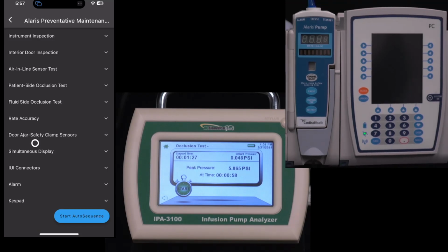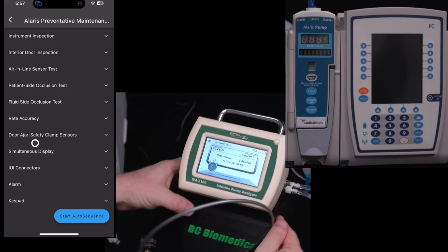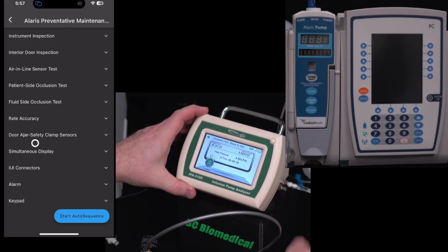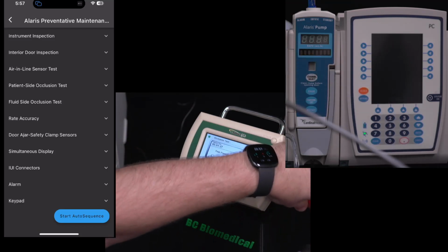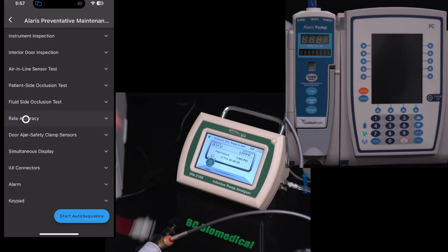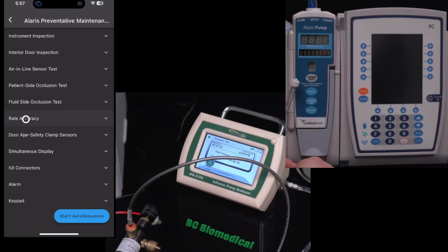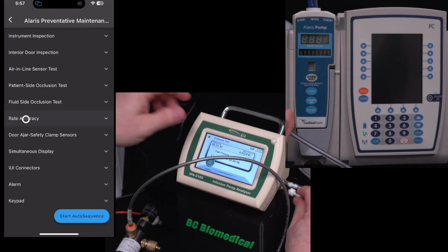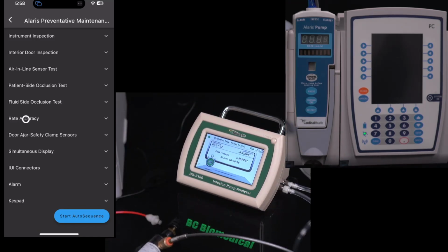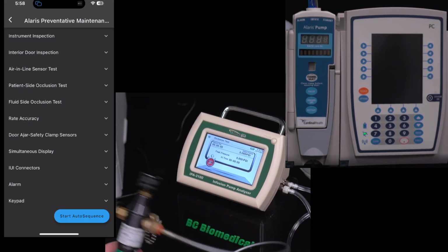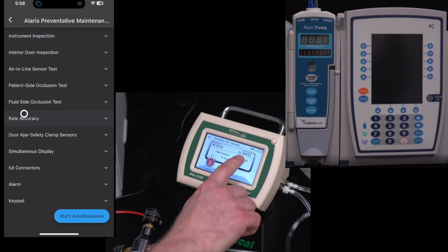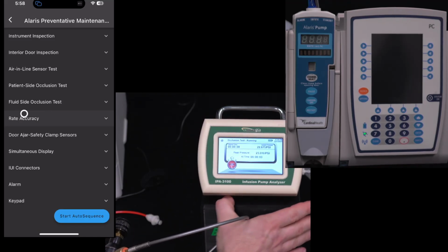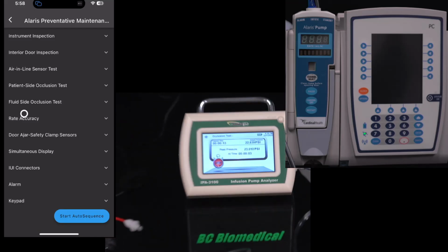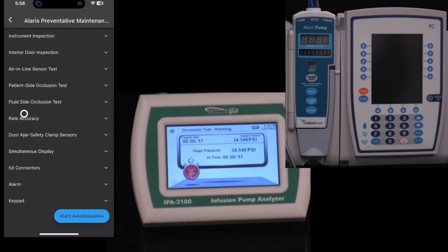So let me zoom out a little bit too, probably this one here. All I have to do is disconnect the inlet tubing here, and I've got my handy dandy hand pump here, so I can plug this in with the correct fitting. It's always a matter of having the wrong fitting, right? So plug that in there, plug this into my hand pump, and then as I apply pressure, I'll hit start. As I apply pressure, now I've got a manometer, and I've got the instantaneous pressure. Let's see if I can show that. Ooh, bad reflection there. Show that right there on the screen. Now you've got a manometer that you can use for calibrating pressure. Good question. And this does go up to 50 psi.